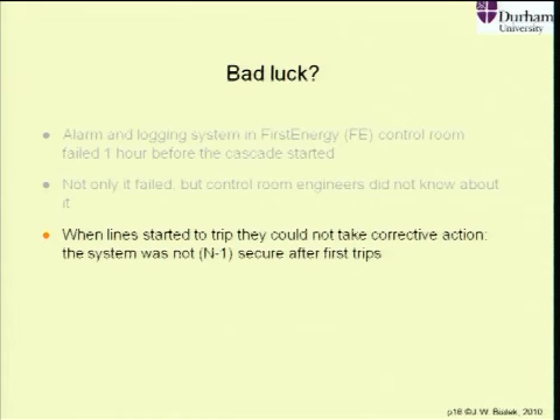Even worse, the system failed, but the control engineers did not know about it. So on their screens everything was fine, and suddenly they were getting phone calls from people saying the lights are off, and they were saying, what are you talking about? We see on our screens that everything is fine. So before they started to take action, crucial time was lost, and by the time they did act, it was too late. Basically, the n-1 condition was not satisfied after the first few trips.